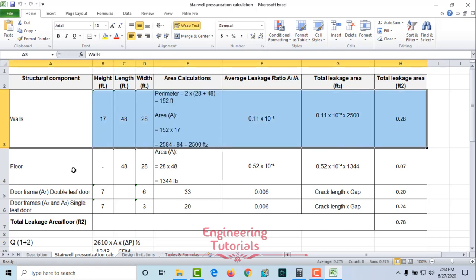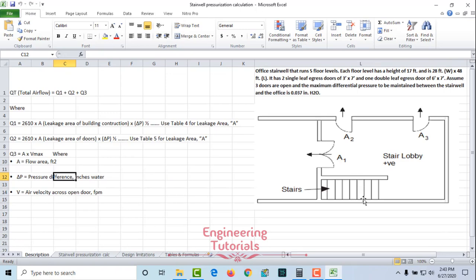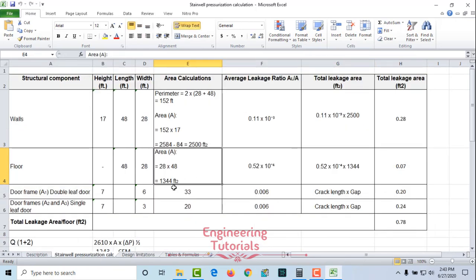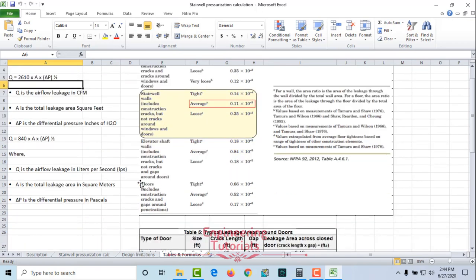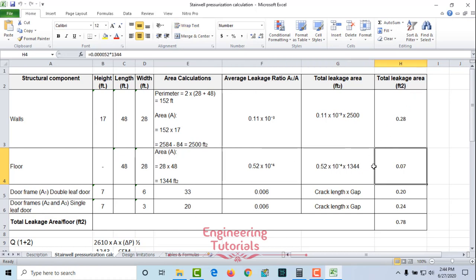Next, for the floor: the floor area is 28 × 48 = 1,344 square feet. From Table 4, the average leakage ratio for floors is 0.52 × 10⁻⁴. Multiplying area by the ratio: 0.52 × 10⁻⁴ × 1,344 = 0.07 square feet total leakage area due to the floor. Q1 calculation is now done.